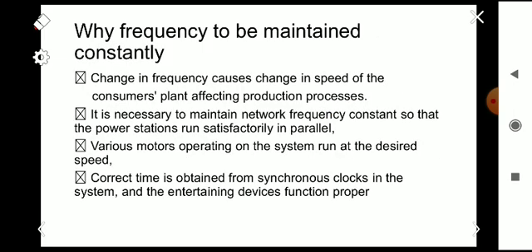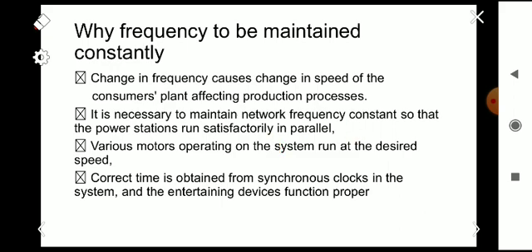Why must frequency be maintained constantly? The change in frequency causes a change in speed of the consumers' plant, affecting the production process entirely. It is necessary to maintain the network frequency constant so that power stations run satisfactorily in parallel — we may connect a number of generators in parallel, and for them to work properly we must maintain constant frequency. Additionally, the various motors operating on the system run at the desired speed, and correct time is obtained from synchronous clocks in the system and the entertaining devices function properly.